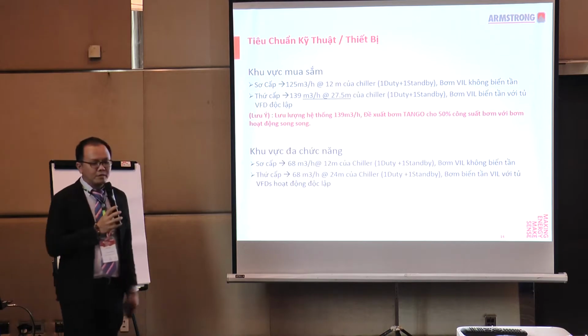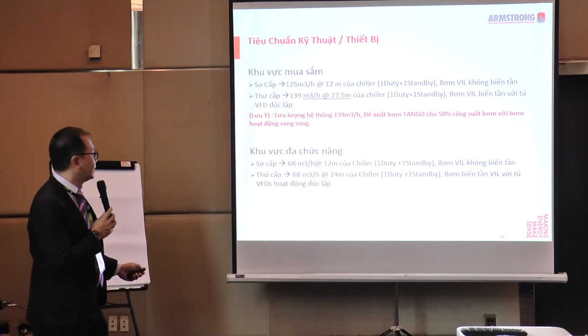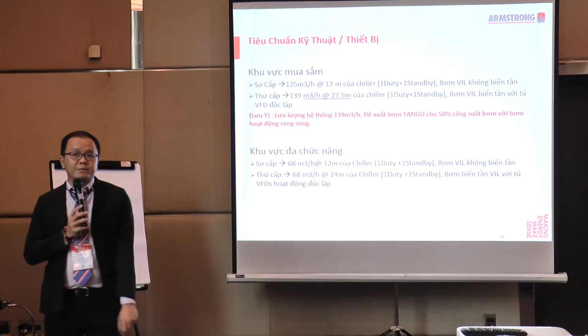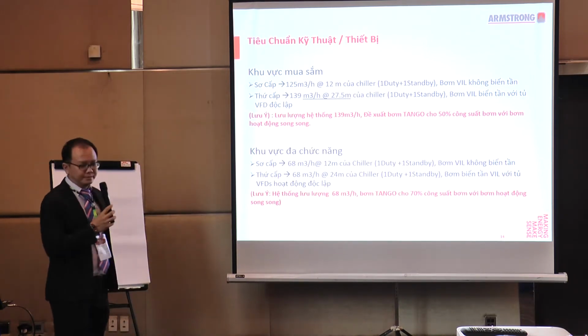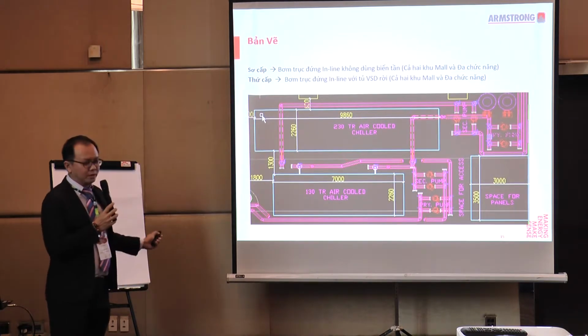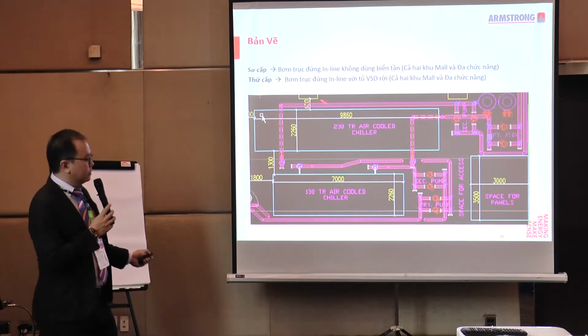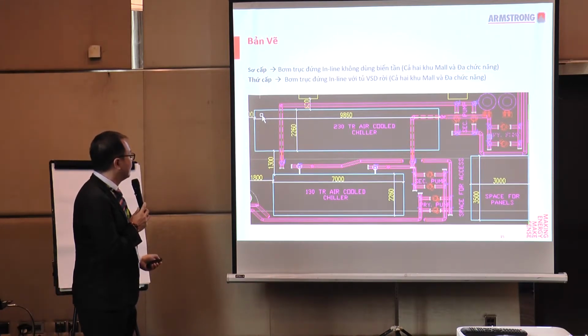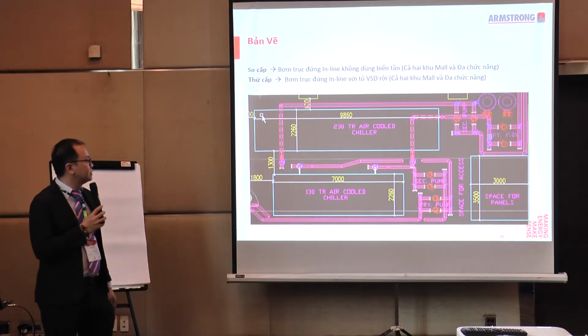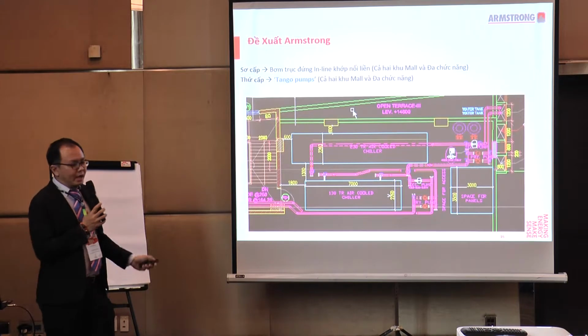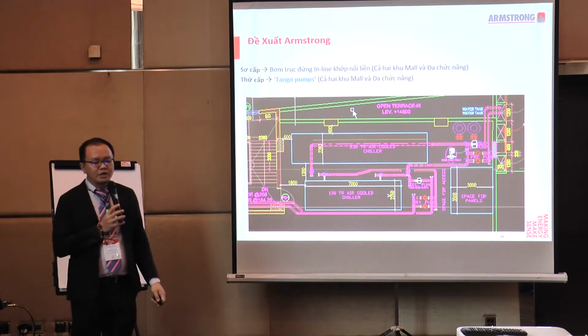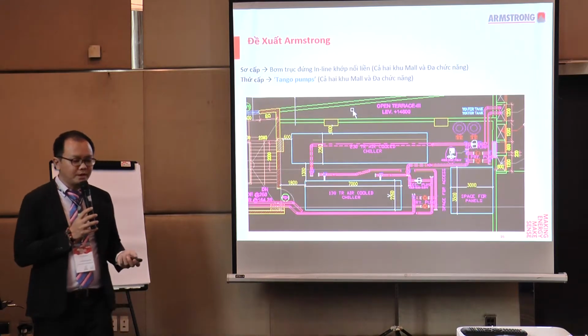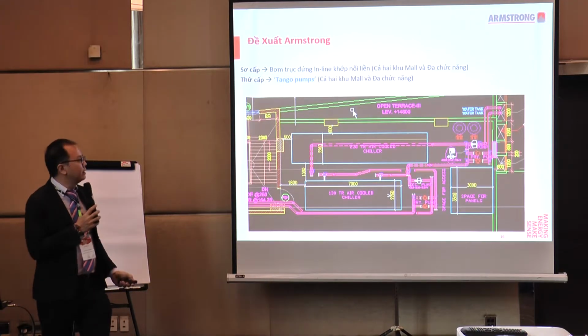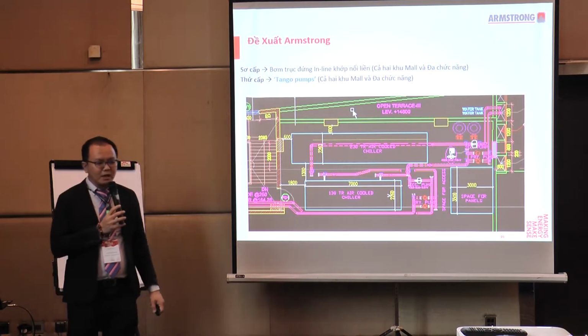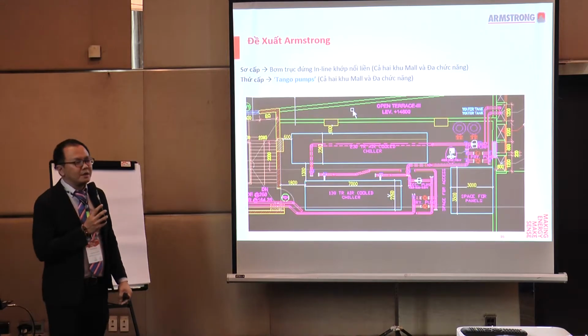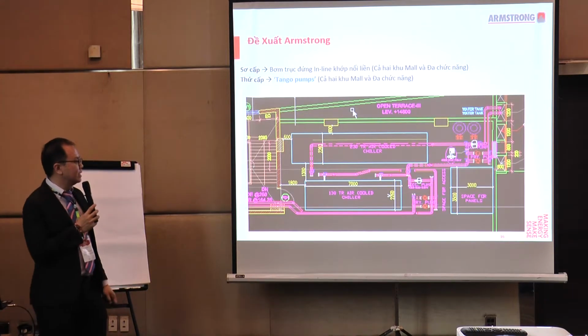But regardless, our pump Tango can offer running at 50% capacity because after all, it's running in parallel operation. The drawing originally is what it looks like for the primary and secondary base. You can see the multiple vertical inline pumps with the attached frequency VFD as well. What Armstrong proposed is changing the secondary to a Tango pump. For both the mall and the multiplex area, the Tango pump helps reduce a lot of the footprint involved, as well as give space savings.